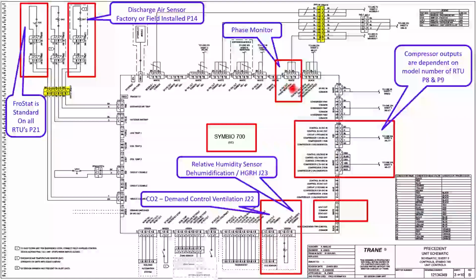Here's our phase monitor. I'll show you a picture of that. Here's our discharge air sensor, factory or field installed. It's going to wire into our Symbio control board. Here's our outside air temperature, and here's our frost stat, normally closed frost stat. Lands down there because it's going to disable compressors if we get a frozen evaporator. Low pressure cutout, pretty straightforward when you're just identifying one component at a time.